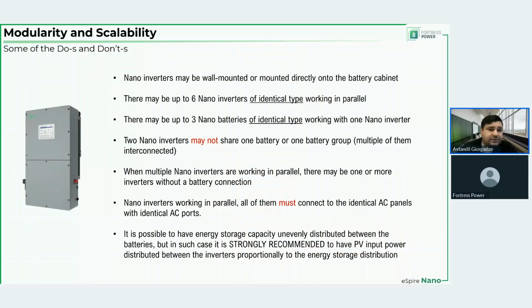The 2 nano inverters may not share one battery or one battery group. So essentially, one inverter will have its own battery or its own battery group, and the other inverter, which is in parallel with it, will have either no batteries or different set of batteries, and these different groups are not interconnected on the DC side. When multiple inverters are working in parallel, there may be one or more inverters without a battery connection, just like I said before. So, for example, you can have, let's say, 3 inverters, each of them having 2 batteries, right? Or 2 of them having 2 batteries and 1 of them having 1 battery.